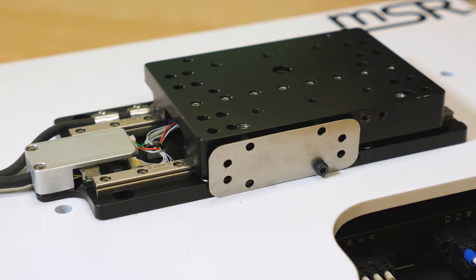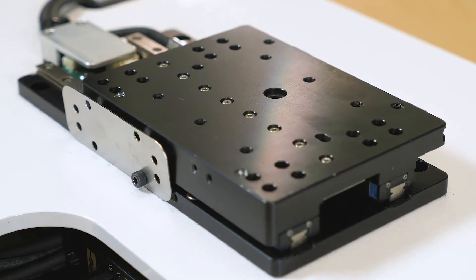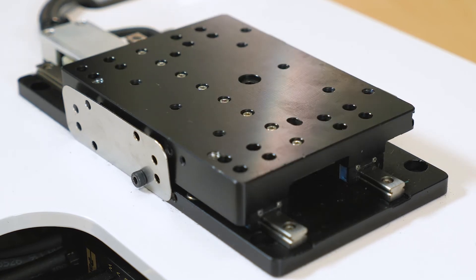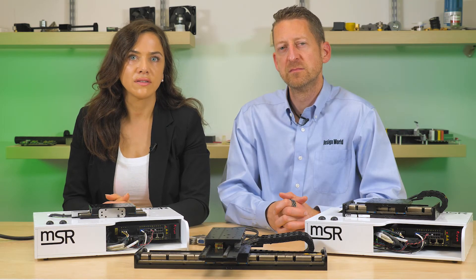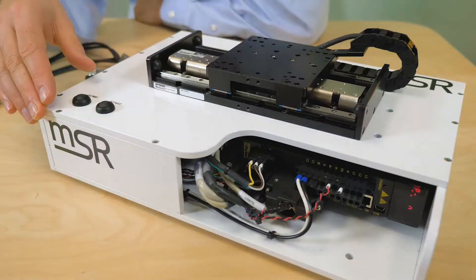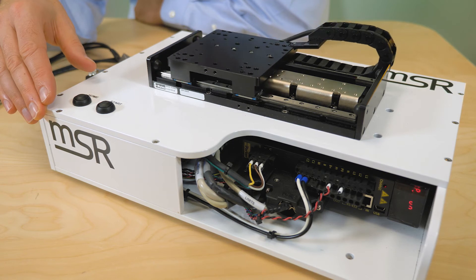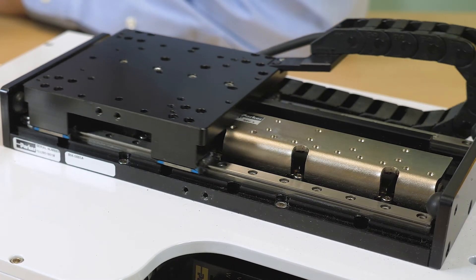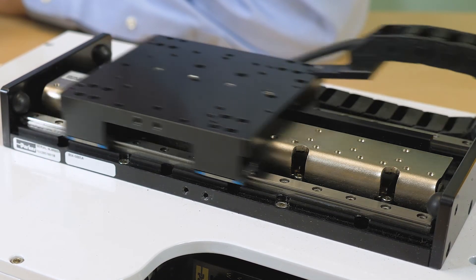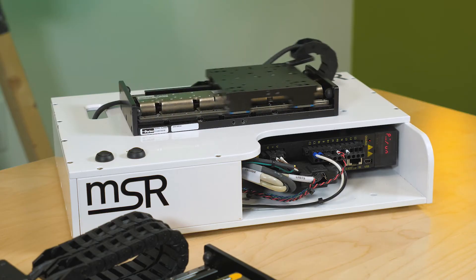This MSR positioner offers instrument builders optimized packaging of the linear motor, guidance encoder, as well as limit and home sensors in one solution. It has been designed with typical instrument regulations and certifications in mind and is both CE and RoHS compliant. Every precision grade MSR is thoroughly tested with Parker's laser interferometer to ensure it meets product specification, and Parker provides test data with a linear slope corrected value noted, yielding higher stage accuracy with controller compensation.